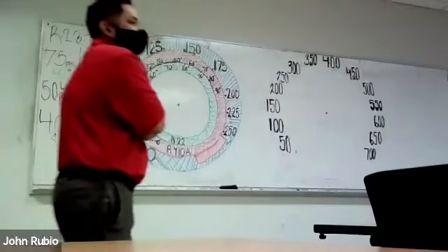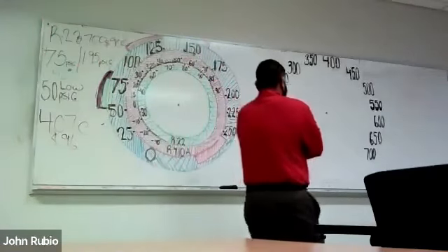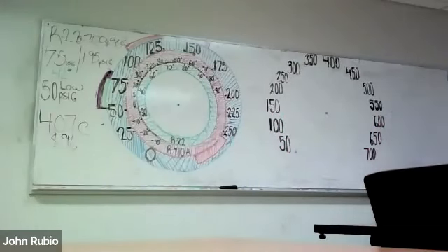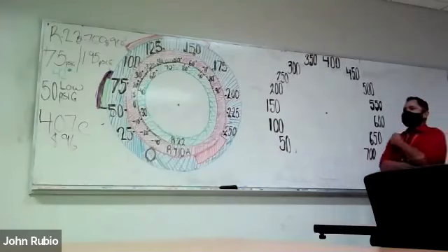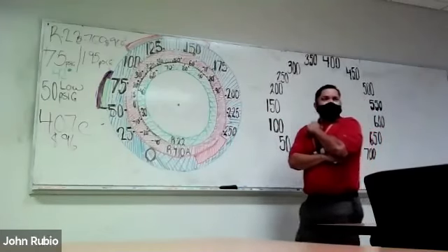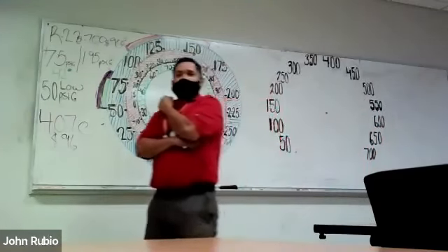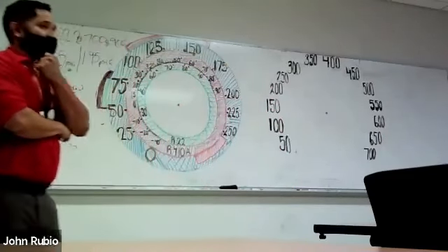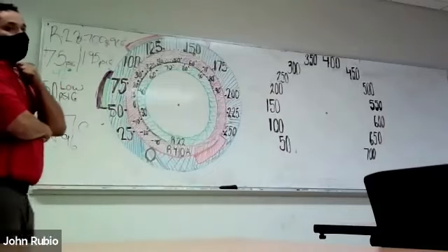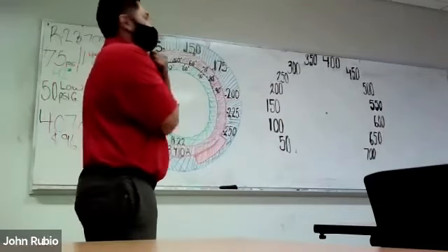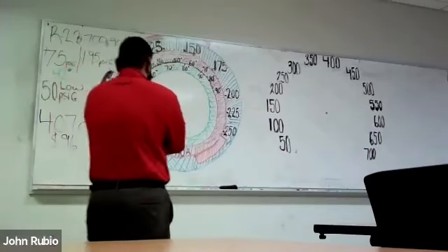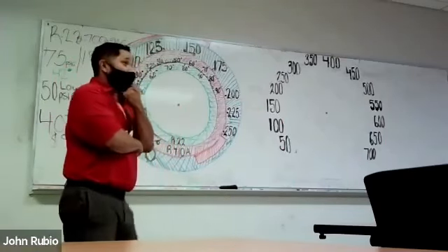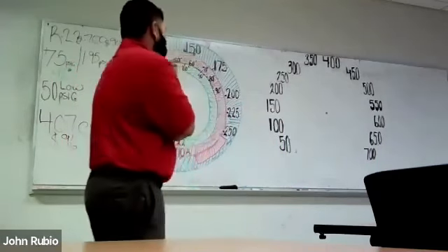Now we understand why systems get low, why they freeze up, why they have the limitations and thresholds. The next thing we have to do, and the final thing here, is we have to find out if a system truly is low on refrigerant. Misdiagnosed low refrigerant is a very common diagnosis where they completely miss and they don't realize it until after they've overcharged the system. And now they have to dump 3-4 pounds right there. Hopefully not in front of the homeowner, but who knows?